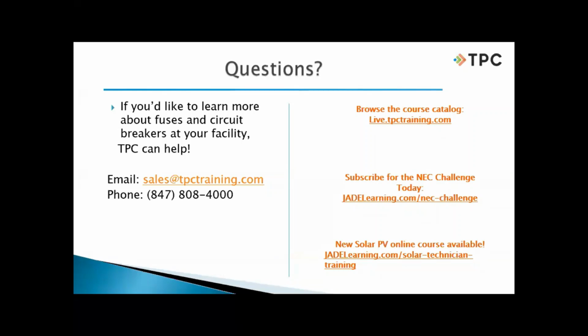When we talk about grounding and bonding, which is Article 250 of the National Electrical Code here in the United States, we call it grounding, and that is a connection to Earth. Why do we do that? To make sure we can dissipate lightning strikes and stabilize our voltage under normal operations. In other parts of the world, they call it earthing, where we connect to the Earth through a grounding electrode, hoping that is a very low impedance path to allow our overcurrent devices to operate.